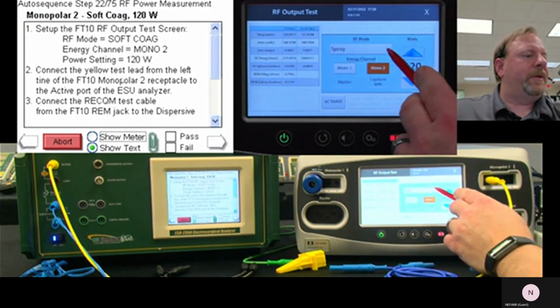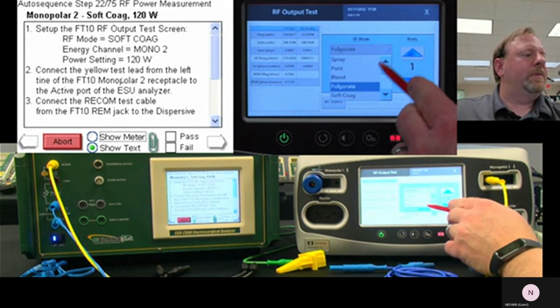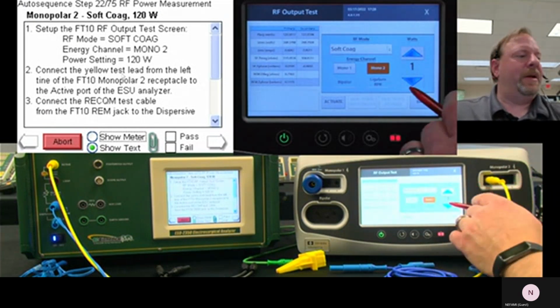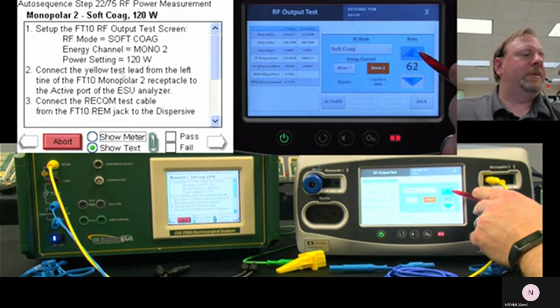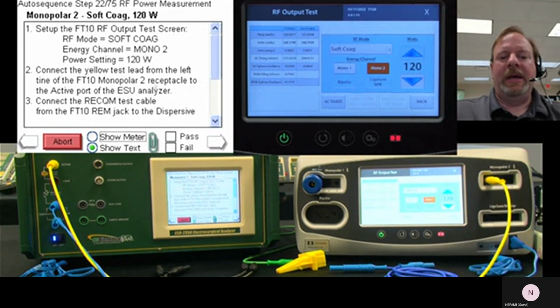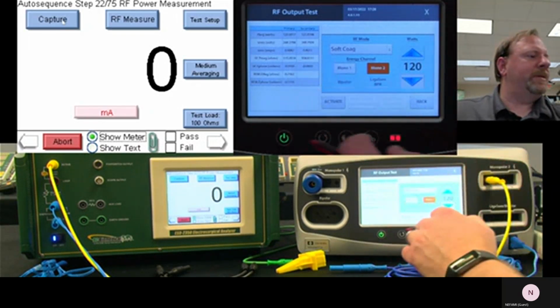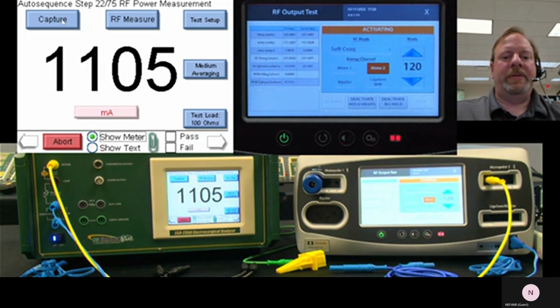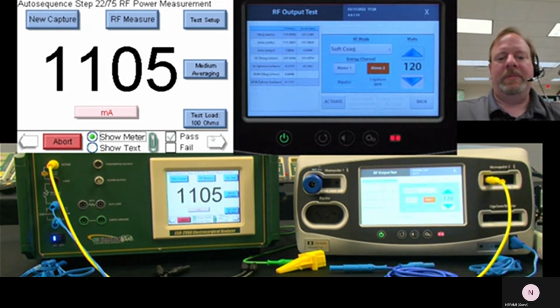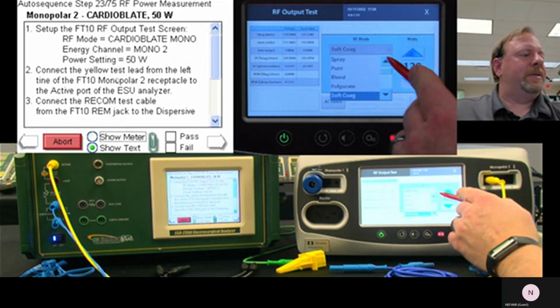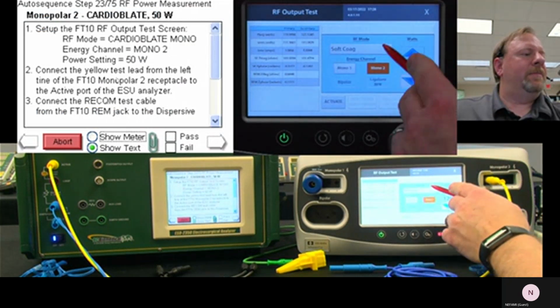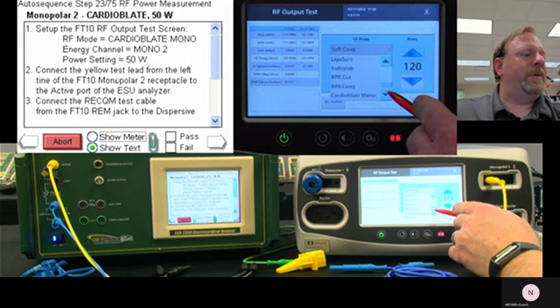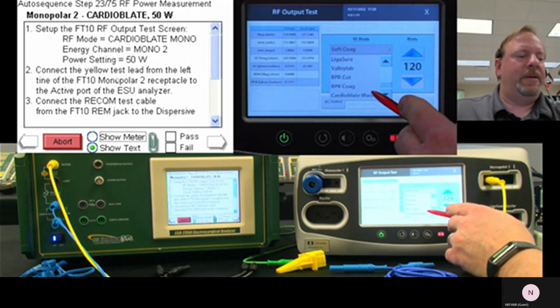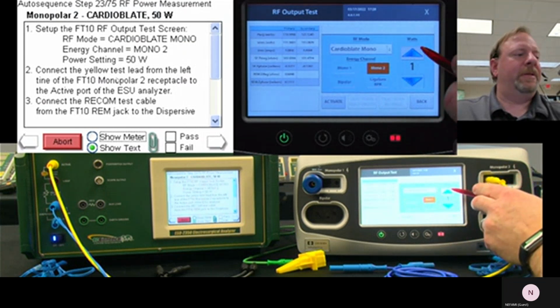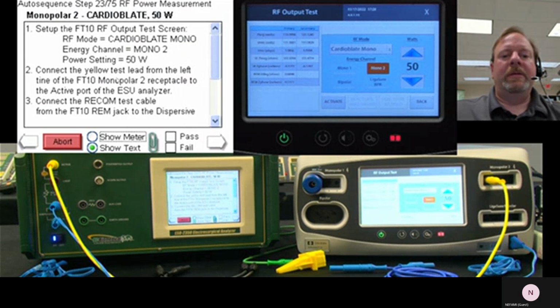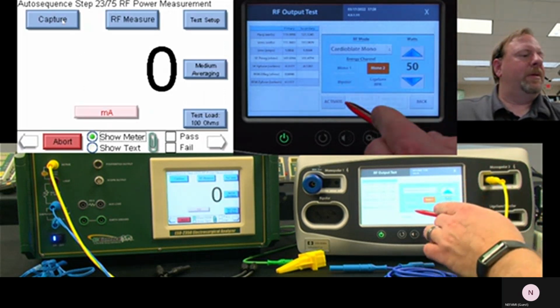So again, we're doing different output modes. It helps when you push the right button. Soft coag, mono 2, 120 watts. They do a lot of maximum power testing, you'll see, especially when doing leakage because you're looking for a worst case scenario. So we activate the generator, get our measurement, move on to the next. So you can see as you get used to this and you do this a couple of times, it gets pretty easy. You can go pretty quickly through this, especially if you remember where the output settings are, whether they're at the top of the list or the bottom of the list. Mono 2, 50 watts, activate.